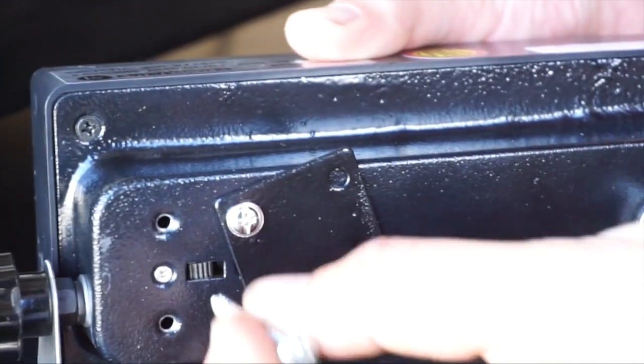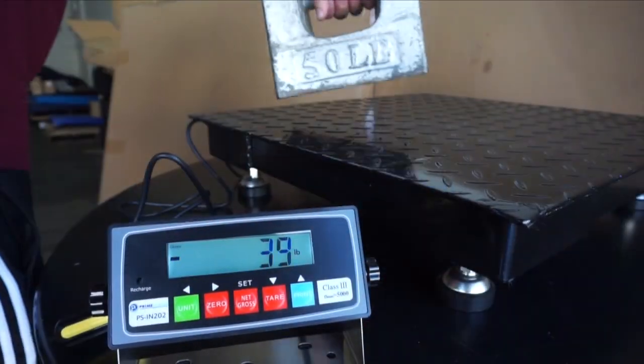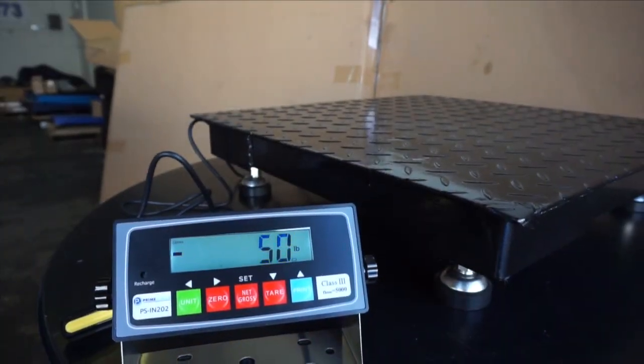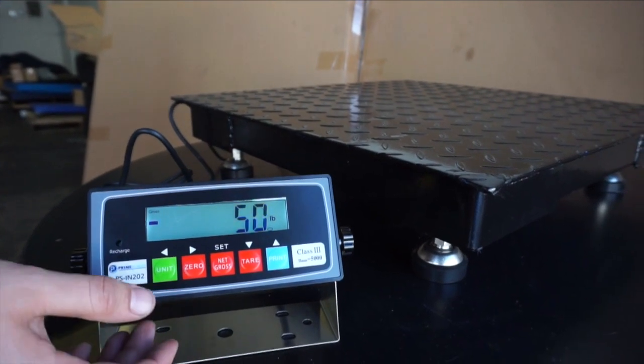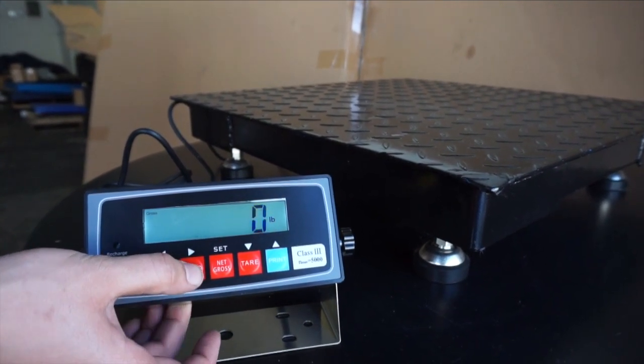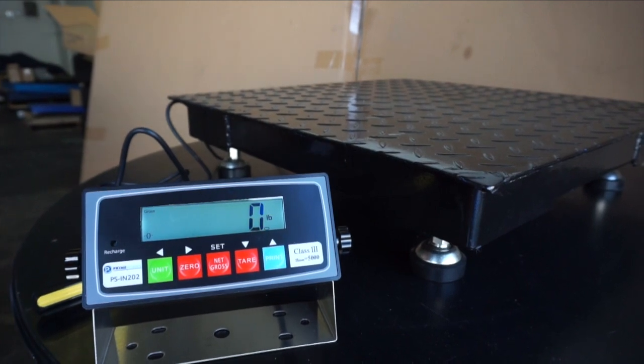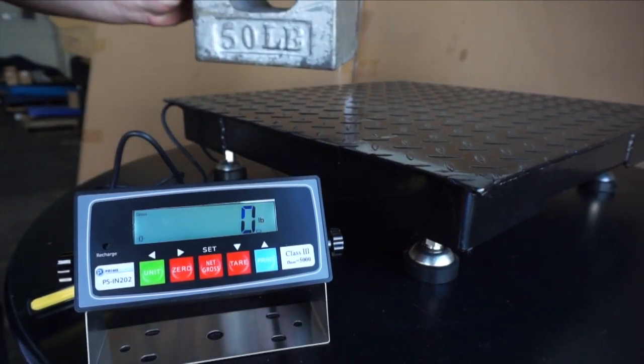Without removing the weight or turning off the indicator, flip the switch in the back of the indicator. You will hear and see the indicator do a countdown from 9 to 1. Remove weight and it should show minus 50 or the calibration weight you used. Press zero and place back the weight one more time.